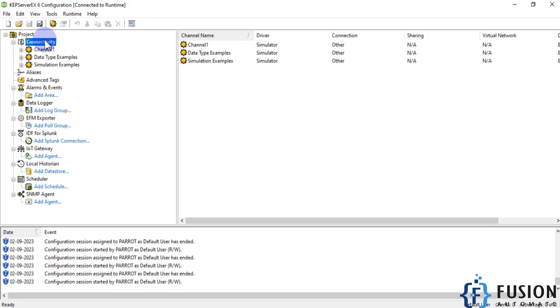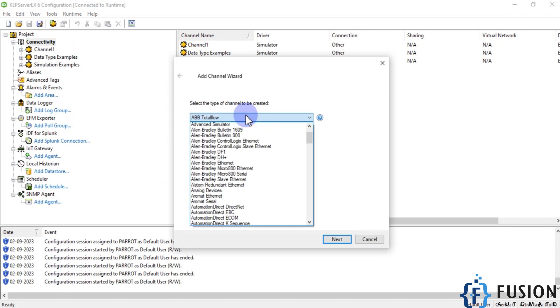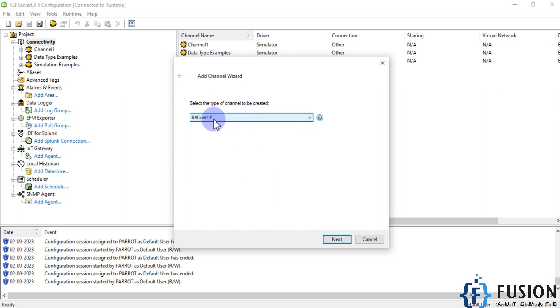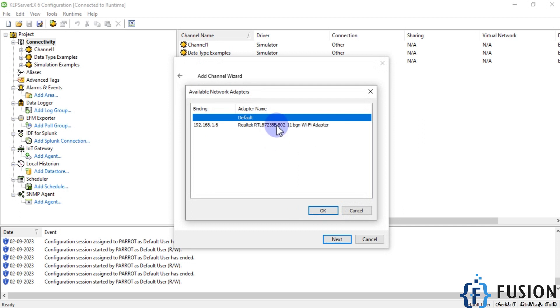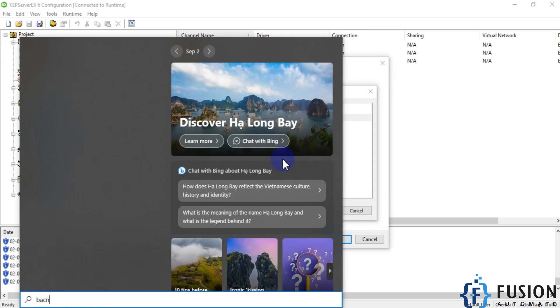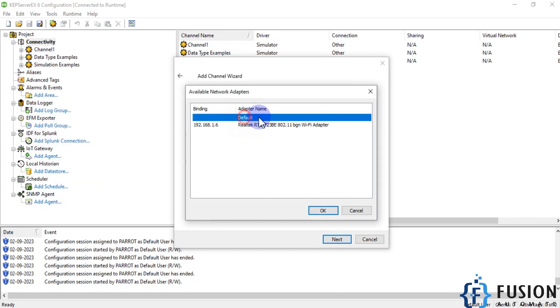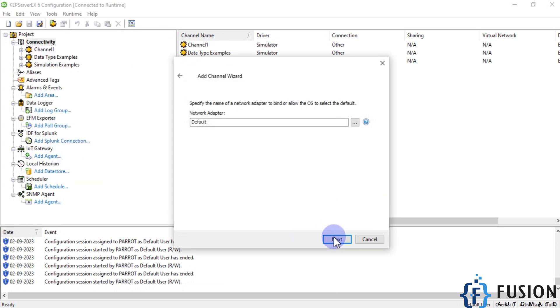Here is my KEPServer. We will go to Connectivity and create a new channel for our BACnet protocol. I'm going to select BACnet IP as the channel type and name it 'back'. For the network adapter, if your BACnet device is a physical device then you select your physical adapter. Right now I'm running my device on my local system — a BACnet room simulator, which is a simulated device — so I'm going to select the default adapter.